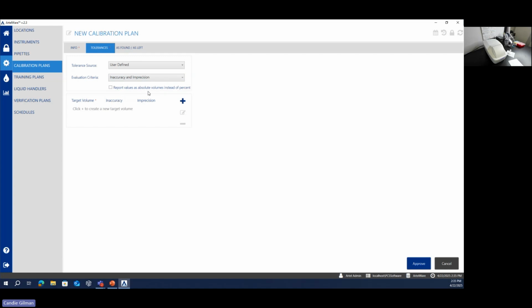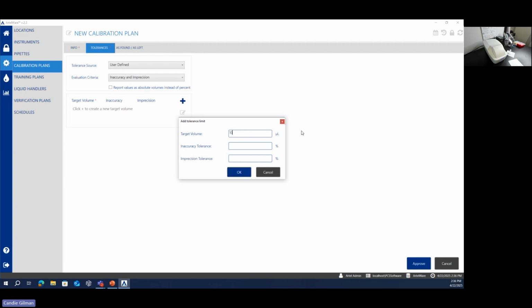And then you also have an option to report your statistics out in absolute volume or percent. I'm going to leave this box unchecked. I like to see the percent because it represents all of the data points as a whole. So now this is where I need to add some volume. So the first volume I'm going to test is 10 microliters. And I have some user-defined tolerances that I'm going to enter in for inaccuracy and imprecision.